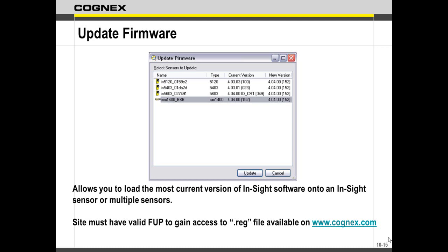But one of the things I want to caution with is that let's say you're doing a program on, let's say, 4.9, and your camera's at 4.4. So you're doing the program, great, great, great. You bring it over to 4.4, and it starts throwing you errors. Now first, if you're not using any of the functions that did not exist in 4.4, the only error you will get is this is a version mismatch. Do you want to continue? Because it knows you've got a newer version coming back to an older version. And all you have to say is, OK, continue. And then if you didn't do anything bad, that's all you have to do. Backs it up to the older version, you're good to go.